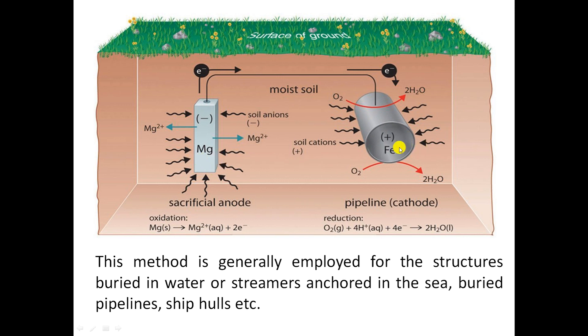Instead of the iron pipe, the magnesium undergoes corrosion. By using a highly active metal, we prevent the corrosion of the base metal. The advantages of the sacrificial anodic method are: the method is very simple and economical; no external power supply is required, because the active metal itself undergoes oxidation and thereby produces the protective current, making the base metal act as a cathode; and it requires minimum maintenance.